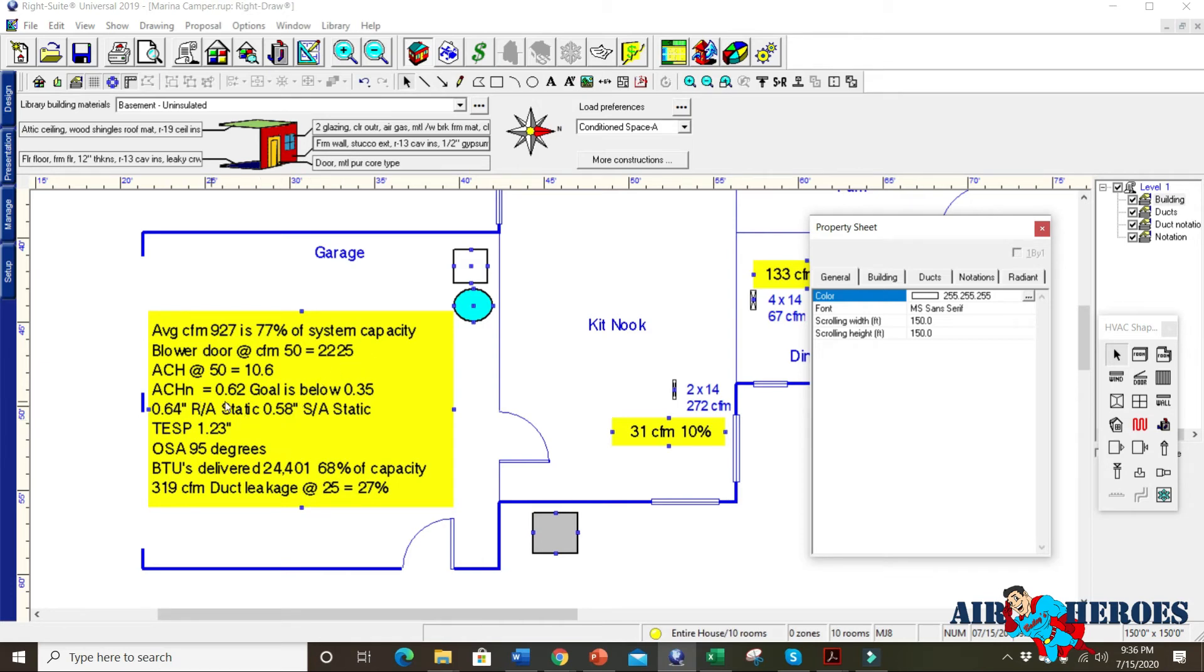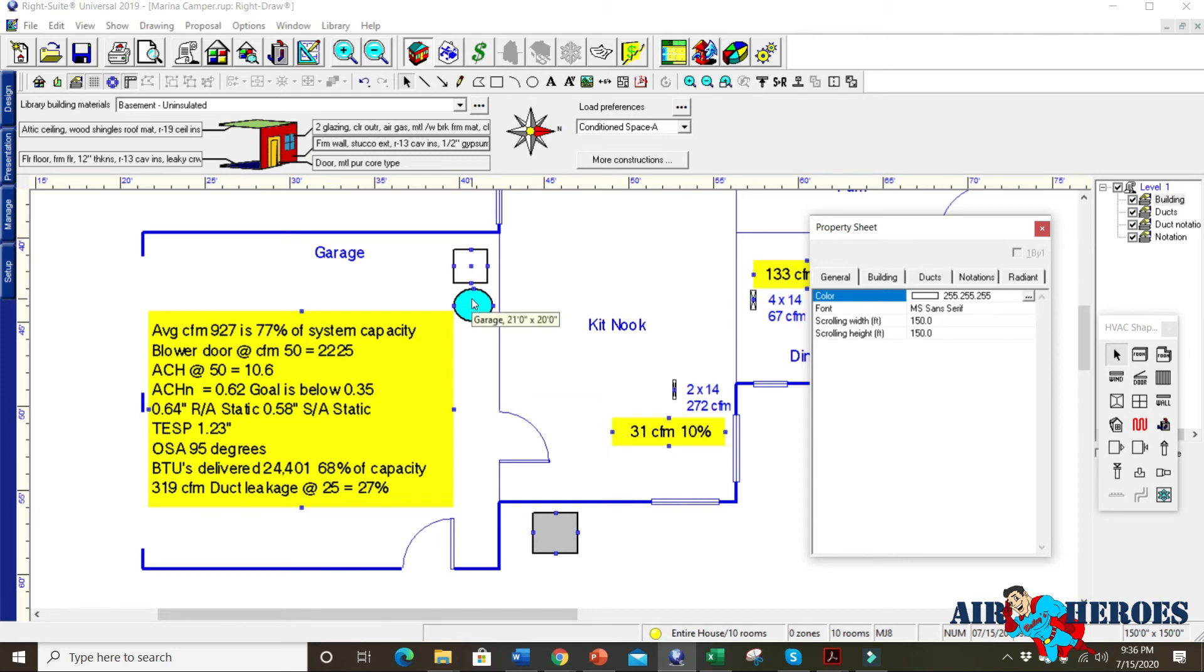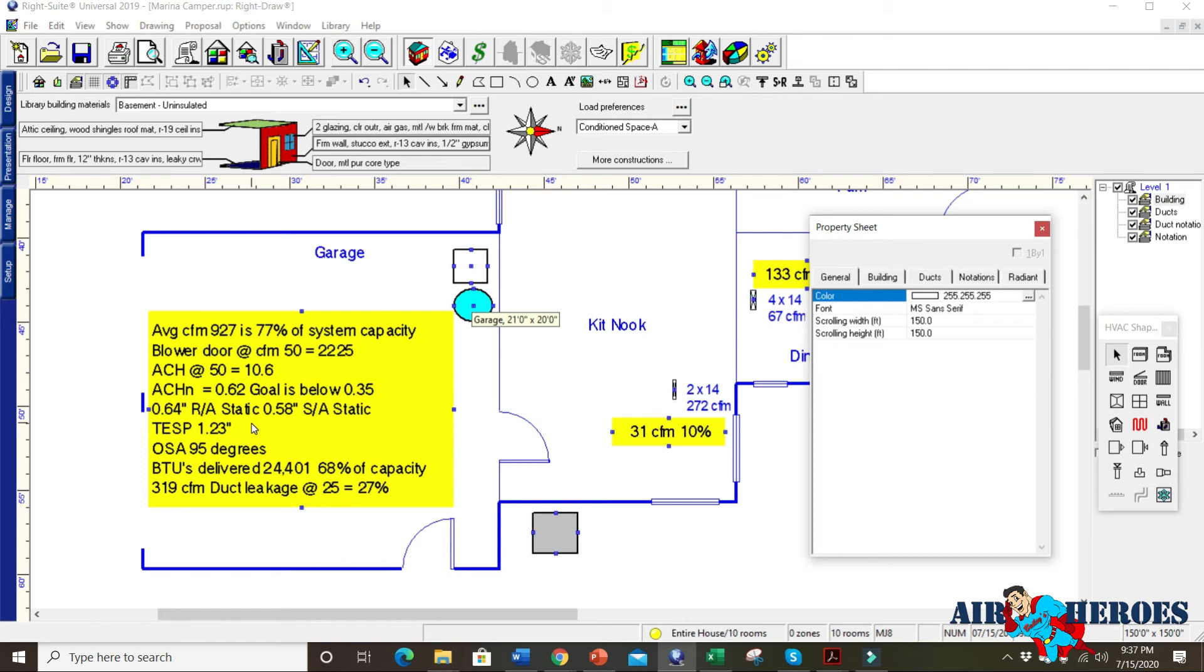There's some other things, all these other readings that we took right here just tells you all the problems they had. They had a three ton unit delivering 24,000 BTUs. It was only 68% of capacity. Remember that National Comfort Institute study. This is typical of what we see all the time. And a lot of times if another contractor comes in here, he just put a bigger unit in and that would totally defeat the purpose because the static pressures here, the 0.64 and the 0.58 and the total of 1.23 means this unit will never deliver the airflow it's supposed to. So the duct work has to be fixed for this system to work.